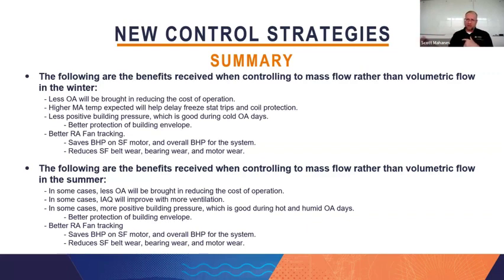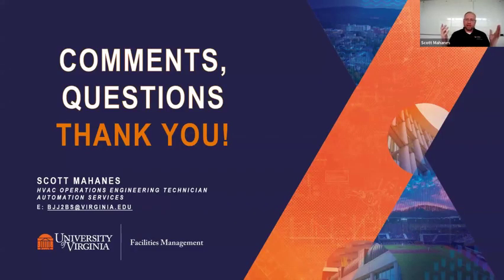This paradigm shift of going to mass flow control gives us perfect control over the air handler system, but it's not always the case when we're trying to do it with volume. In fact, the only time volume is going to work is if you have 70-degree outside air, 70-degree return, 70-degree supply air. And that's never going to happen. And so hopefully you can use this information to look at how you allocate your CFM. And for the future, this wouldn't be for TAB professionals, but you can look out for control strategies that are going to utilize mass airflow control versus volume. Okay. That's all I have for you right now.